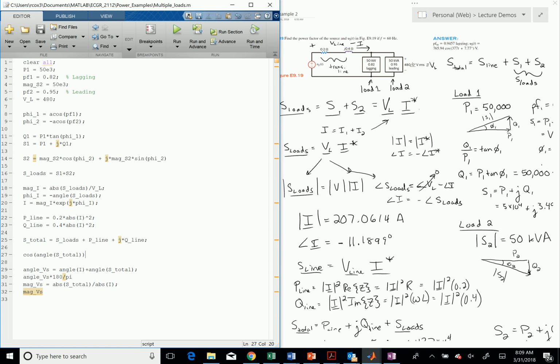Very often my loads are defined to me in terms of the powers and reactive powers that those loads demand, as opposed to being told an impedance. And I might be told an impedance of a transmission line like I am right here. All right, and this is also pretty common where you say, well, the load has 480 volts. Utility is required to provide a certain level of voltage at an individual customer. And then V sub S needs to go up or down to make sure the customer gets that 480 depending on what this transmission line is.